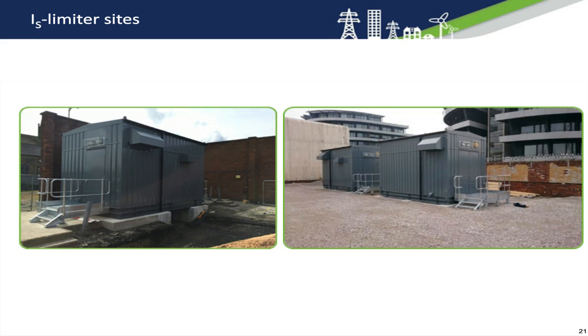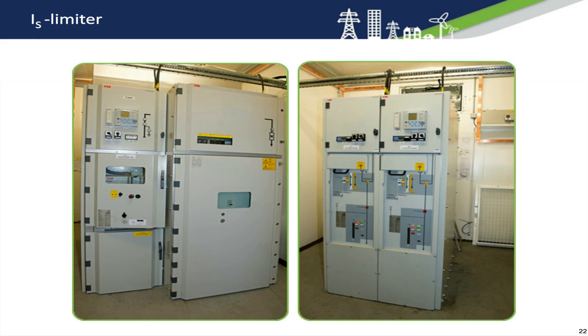Inside these 2 containers, the photo on the left is the IS limiter, which is made up of 2 parts. The first, on the far left, is a circuit breaker controlling the IS limiter, which provides a 3-phase trip when any of the IS limiter fuses blow. Attached to that is the IS limiter, which is a horizontal withdrawable fuse on a carriage. The photo on the right is the bypass switchgear at Broadheath.